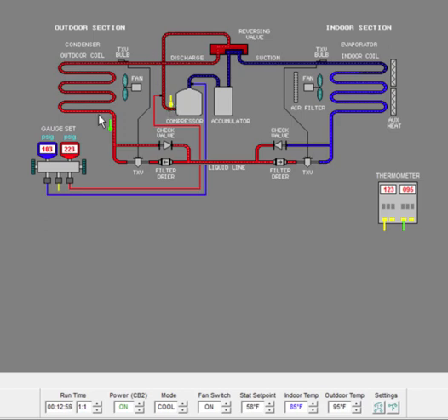Now let's just review real quick what a condenser is supposed to do. It takes the heat from the entire system, which is contained in the refrigerant, as it leaves the compressor. This is my discharge line. This is going to be a high temperature, high pressure vapor. It is a superheated vapor, which just means it's heated over the point. There's a lot of sensible heat in it that's over its condensing temperature. Okay, we come out our discharge line. We enter into our outdoor coil, which in this case is the condenser coil.